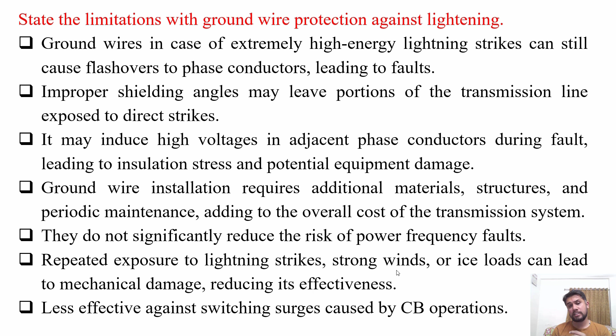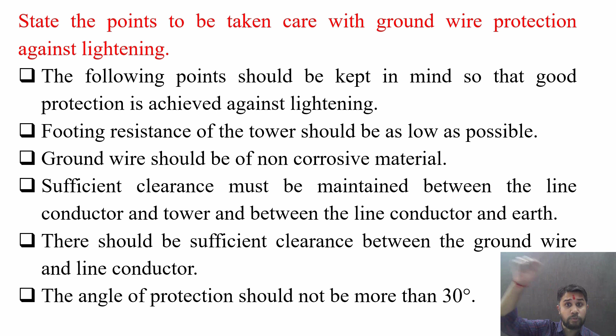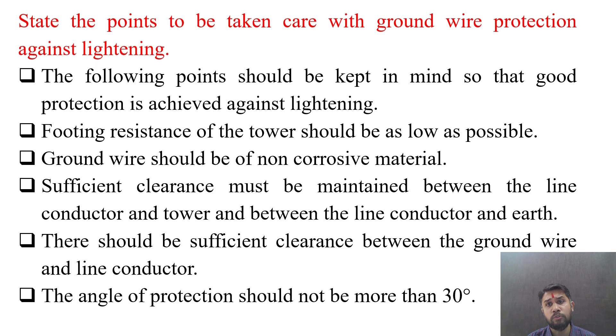So footing resistance of a tower should be as low as possible so that the ground wire can work effectively and easily ground the lightning strike. Ground wire should be of non-corrosive material. Sufficient clearance must be maintained between the line conductor and tower and line conductor and earth. There should be sufficient clearance between the ground wire which is on the top of the tower and line conductor. The angle of protection should not be more than 30 degrees.